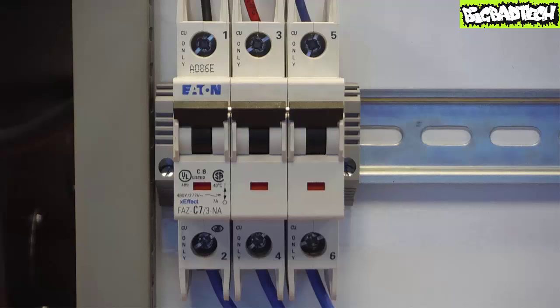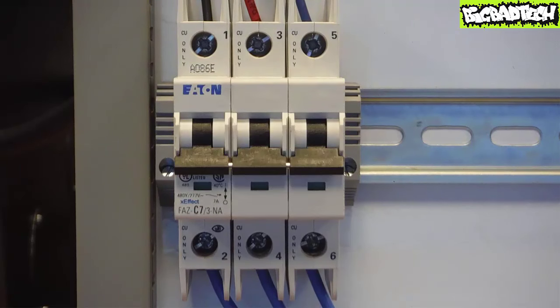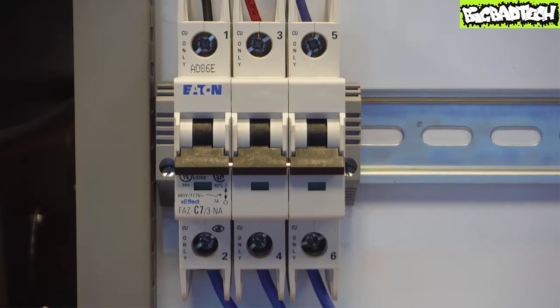Ordinarily the closure of this contactor would be a bad idea under full sail. However the moment the phase-to-phase event occurs the circuit breaker recognizes the high current event and opens up to save the day.